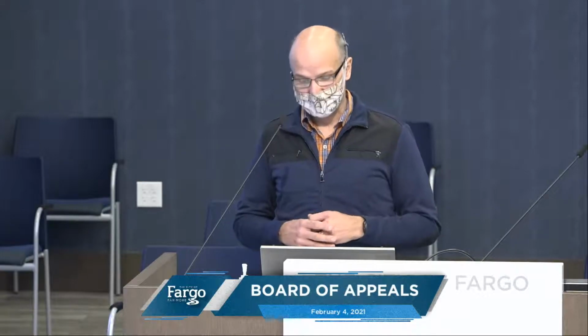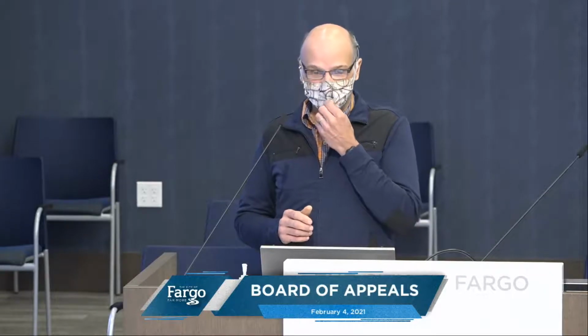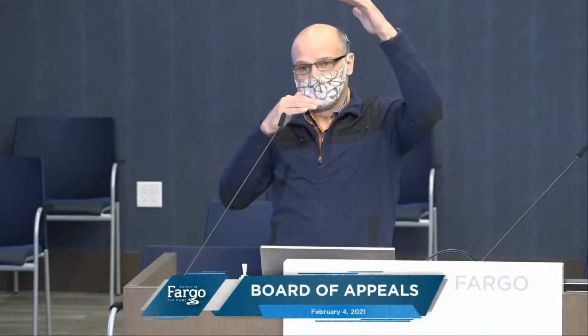Now, I hesitate to even raise that point because I don't want this Board of Appeals to think in any way that we feel that hardship should require any sort of a variance. We're not asking for a variance. The overhead clearance in level 2 of that garage is 7'4". A typical overhead fire door, the one that comes down automatically, has fusible links, coils up, rolls up, we've seen them before. Minimum 22 inches of clearance above open span. That would create a 5'6" maximum open span in a garage door. We'll accept that.